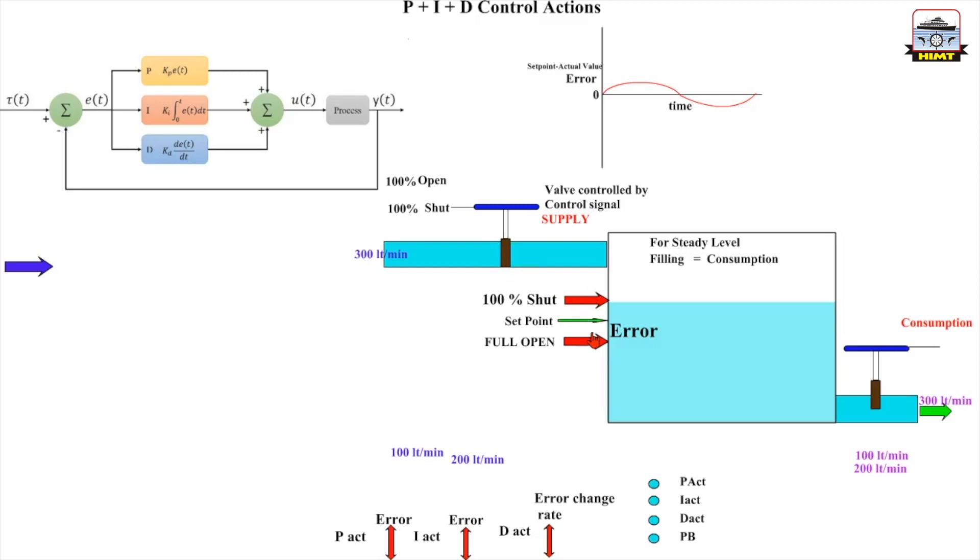So this adjustment is in simple terms called the proportional band. The narrower the proportional band, I can reduce the maximum deviation.